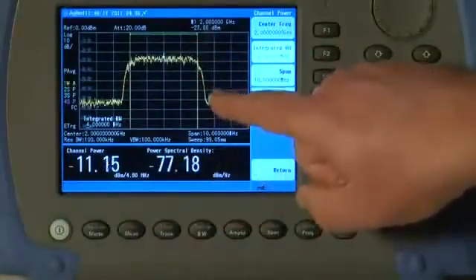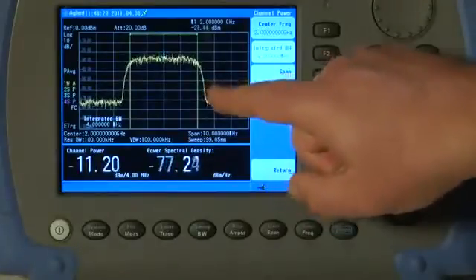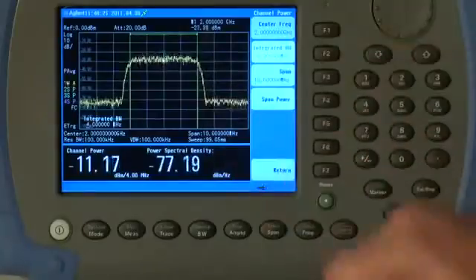What is now happening is that the analyzer is integrating under the curve, in other words counting the squares, adding up the total amount of power within these green channel power markers.